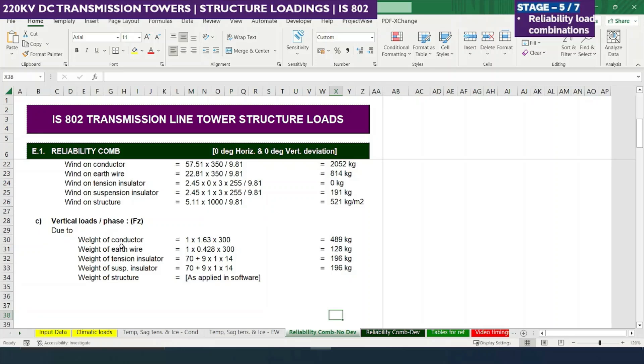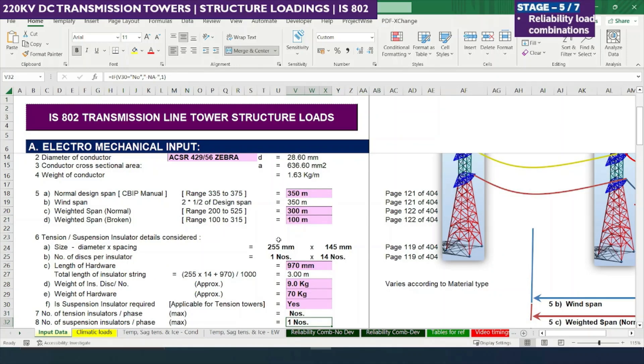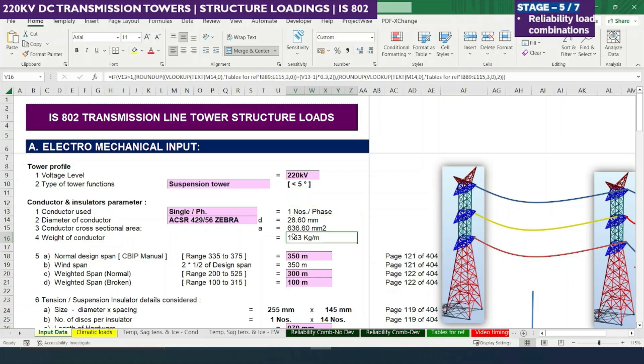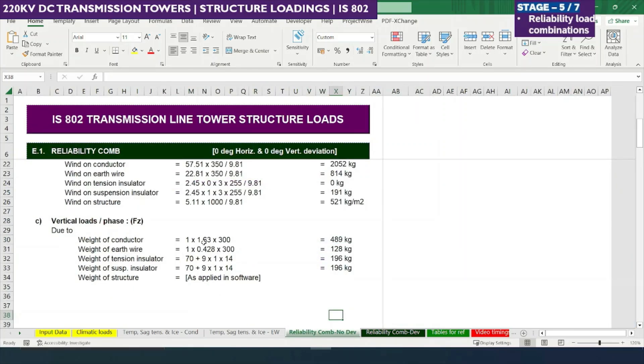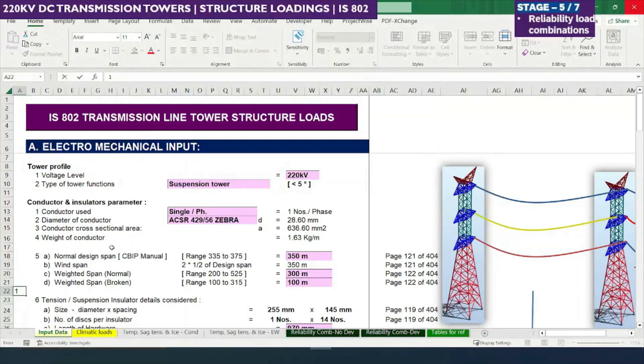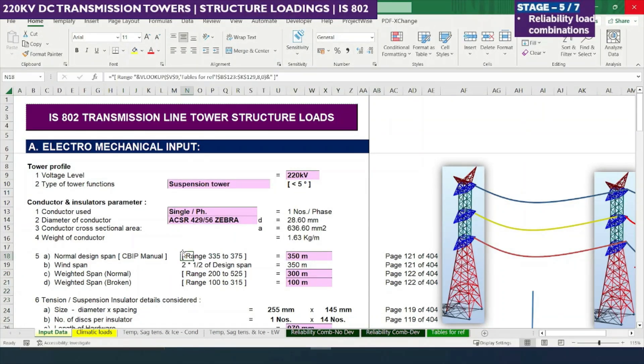For vertical loads, we consider the vertical load due to the self weight of conductor. The conductor weight is 1.63 kg per meter as seen in the electromechanical input. It is a single conductor, so: 1 (quantity) × 1.63 kg/m × 300 meters (weighted span). Here the weighted span of 300 meters is used.